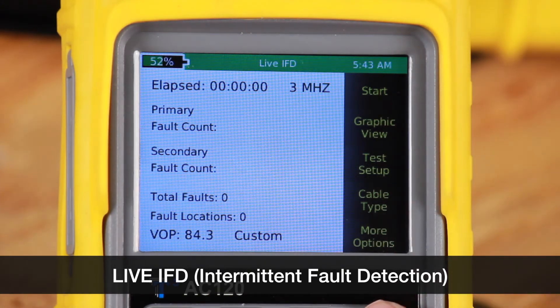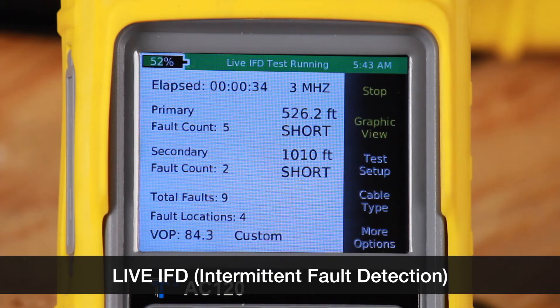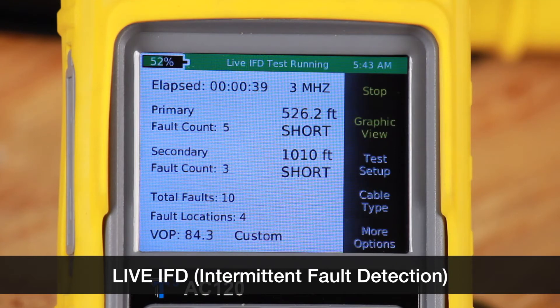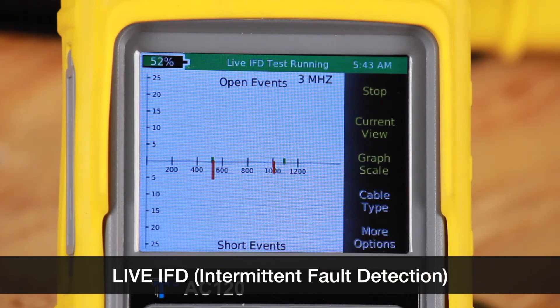To start the test, press the start icon or the green button. The test has started, and you can see the elapsed time in the elapsed time section. We can see our first fault — 520 feet to a short. We have one fault so far, then two, three — and you can see the primary fault, secondary fault, and total fault counts. In graph view, the tickers indicate how many faults occurred at each location and at what distance.